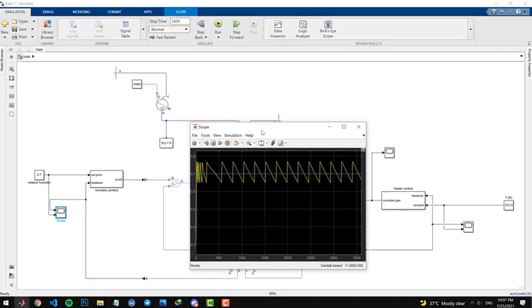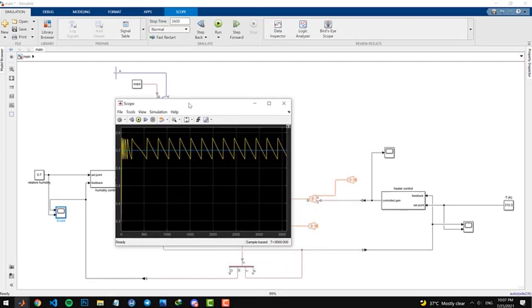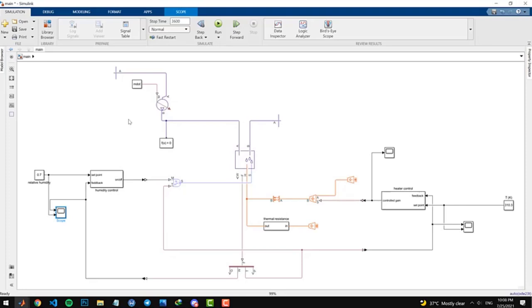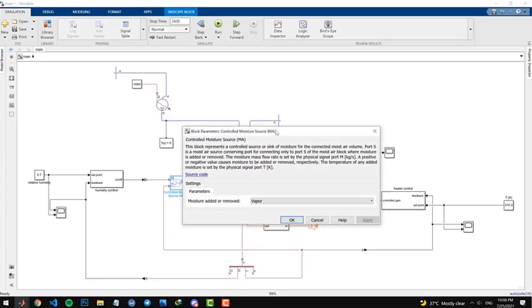Now let's take a look at our humidity control loop scope. As expected, we have the periodic on/off behavior from the relay control, with an upper bound of five percent around the 70 percent set point. It works very well. In one hour we have around 15 to 16 turn-on events, which is fine — we should check the actuator specifications but it doesn't seem excessive.